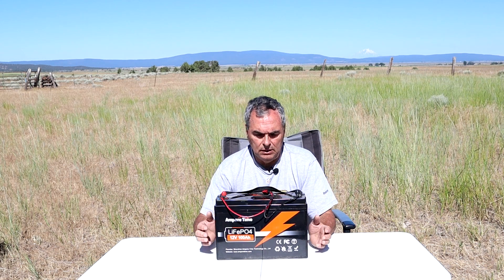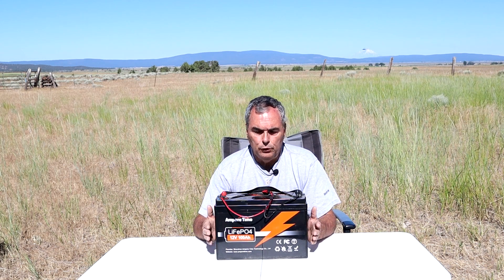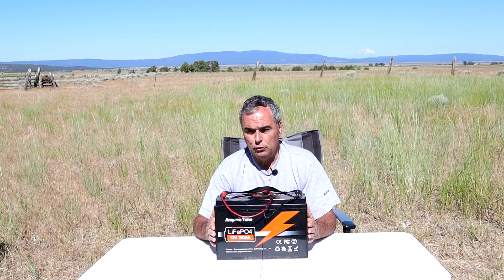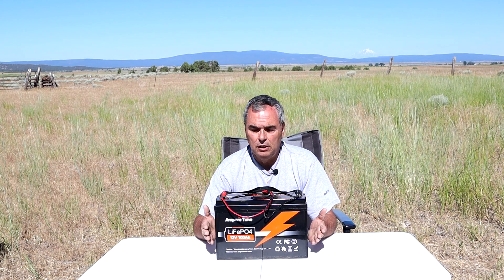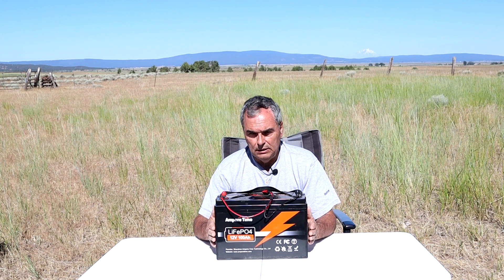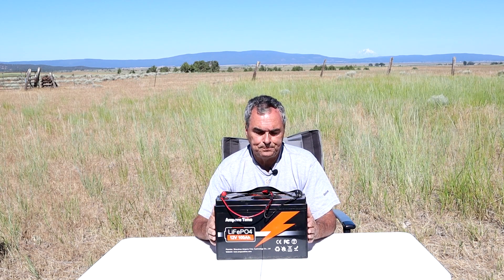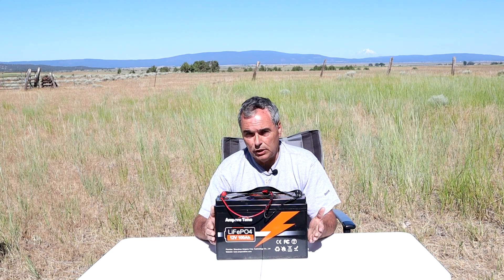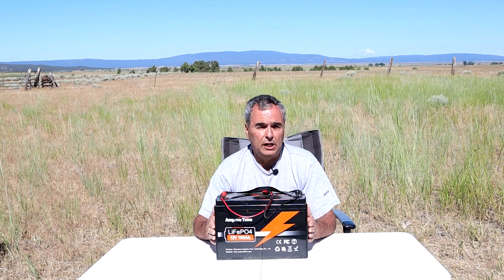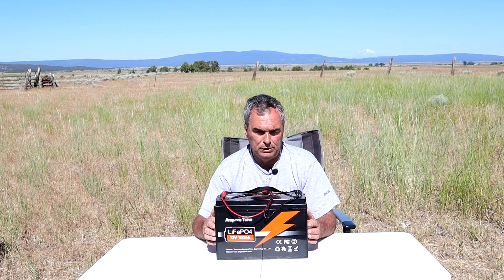Now let's talk about the operating temperatures. For charging, you must be above 32 degrees Fahrenheit and can charge up to 122 degrees Fahrenheit — that's 0°C to 50°C. For discharging, you can discharge this battery down to minus 4 degrees Fahrenheit up to 140 degrees Fahrenheit, which is minus 20°C to 60°C.